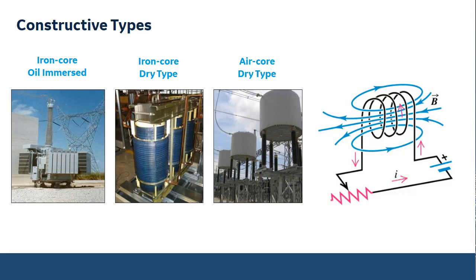So the first one, iron core oil immersed, as the name says, the reactor has an iron core. So what does having an iron core mean? The main difference is that an air core is, as the name says, one that has no core. And the iron core is basically a forced path that's placed right in the center of the coil.